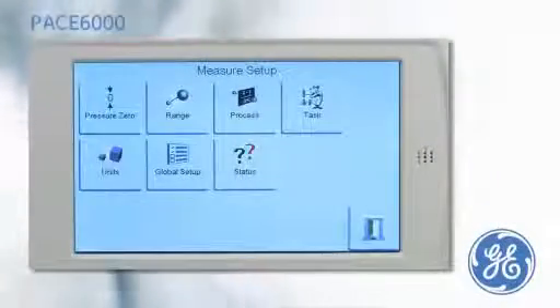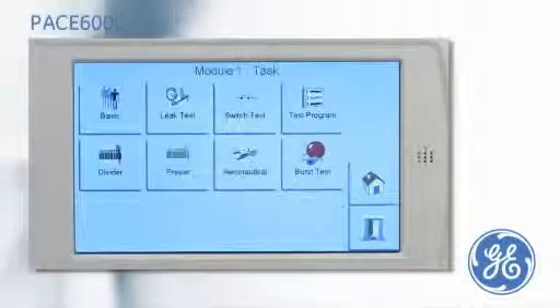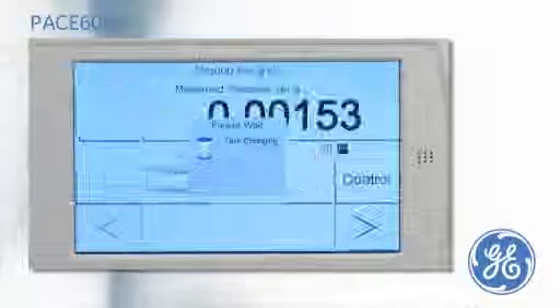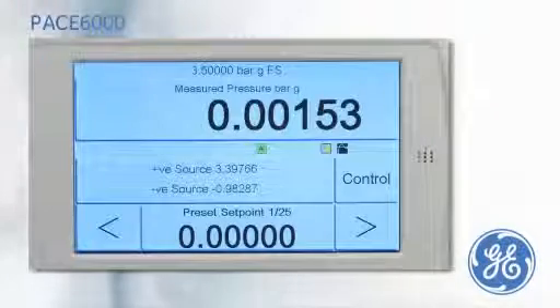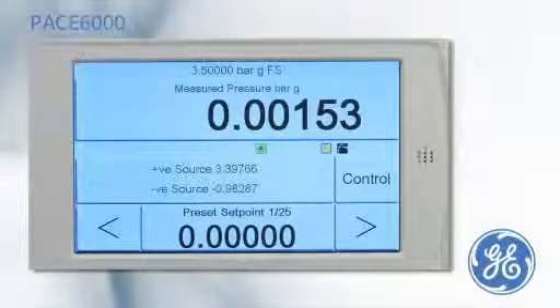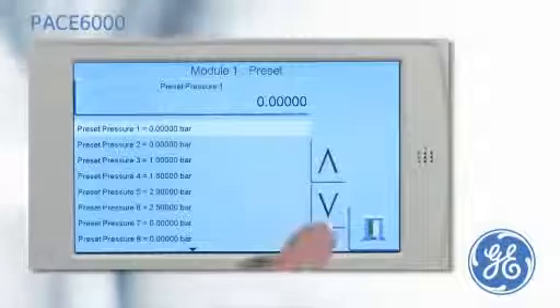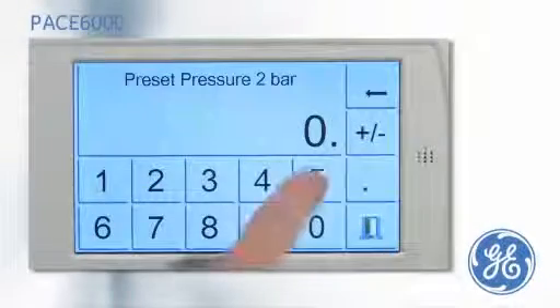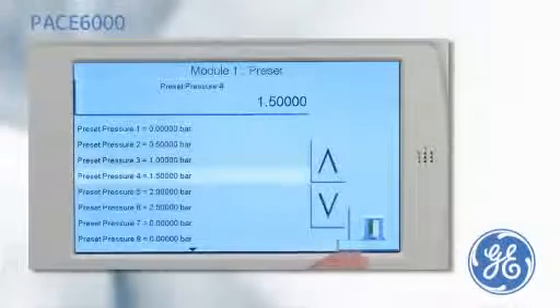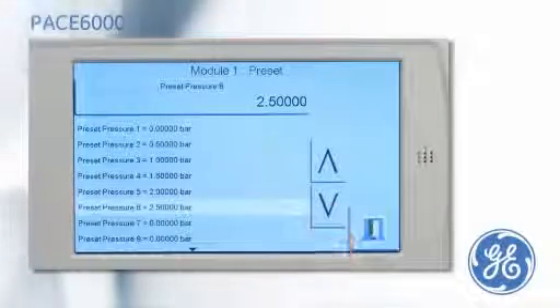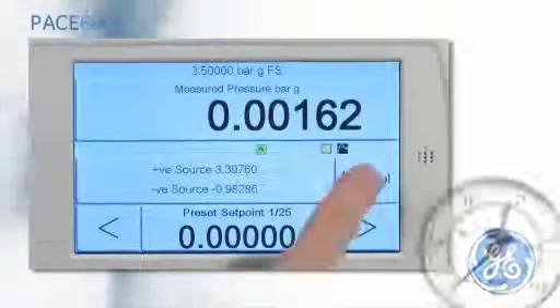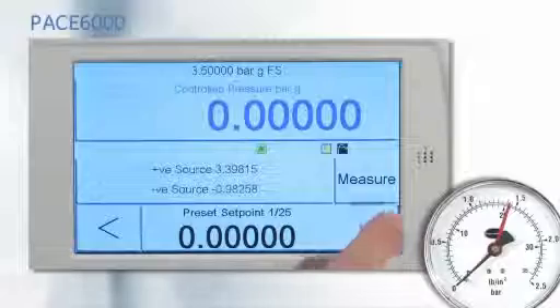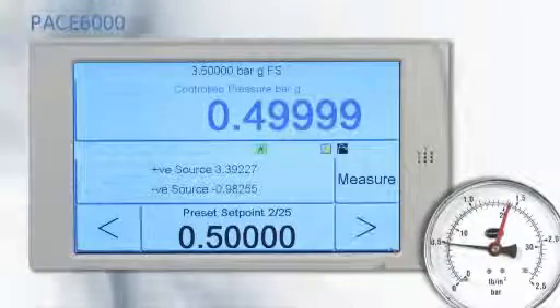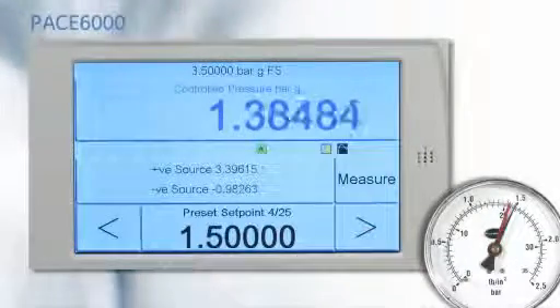The preset task works like the divide task, but enables the user to define the pressure set points, meaning that a non-linear calibration can be performed. The first preset is 0. We set preset 2 to 0.5 bar. Preset 3 is 1. After the PACE has been put into control mode, the pressure can be stepped through the cardinal points by simply pressing the nudge buttons.